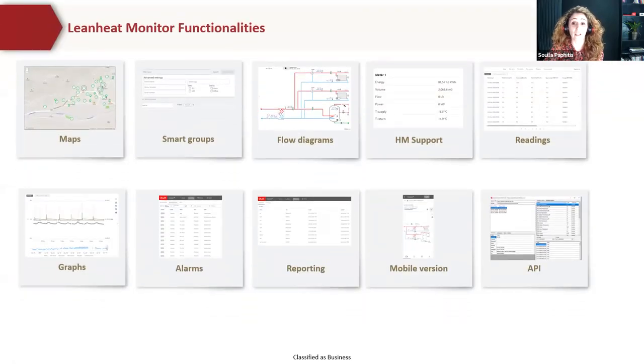So with this intuitive software, you can access a wide range of functionalities, and it's so important when you're looking at the controllability of the product that you've got on site. Not only is selecting the right heat exchanger and the right valve important, but actually understanding how they're working and how your system is operating. With this software, you get a number of functionalities, including maps, flow diagrams, real-life data, understanding what your flow and return temperatures are and what you're actually delivering from your heating circuits and your domestic hot water. You're able to download the files as CSV files, and you're also able to create charts and graphs so that you can actually prove and show how your system is operating.